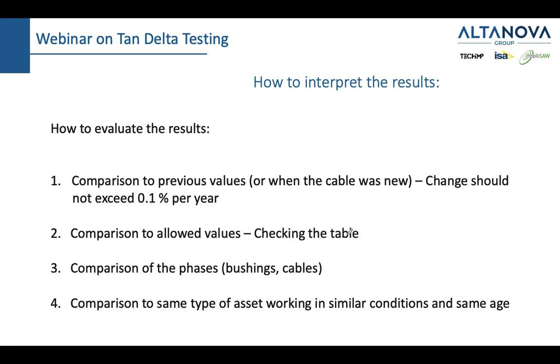How to follow tan delta according to trend recording, because one of the slides stated that the evaluation is not only about comparing to a specific value. So that's a good question, and thank you for that. So one could say that if you measure tan delta on a yearly basis, the absolute maximum of change which can happen is 0.1%. Again, it's not written in stone. The new, I would say, standard is being written, and this will be included. But if you have a new transformer which has tan delta of 0.3, and after 5 years you measure that transformer and the tan delta is 0.9, which is still below 1, that's a sign for an alarm. So let's say that the rule of thumb would be 0.1% per year or less.